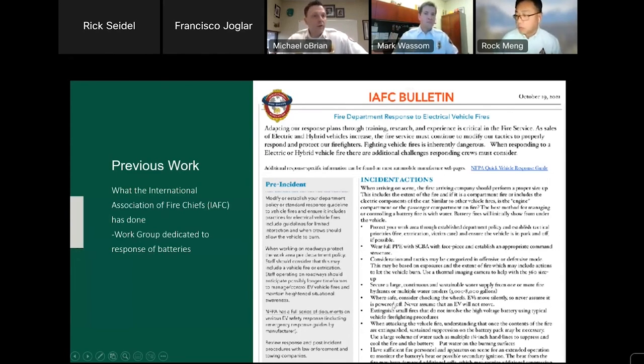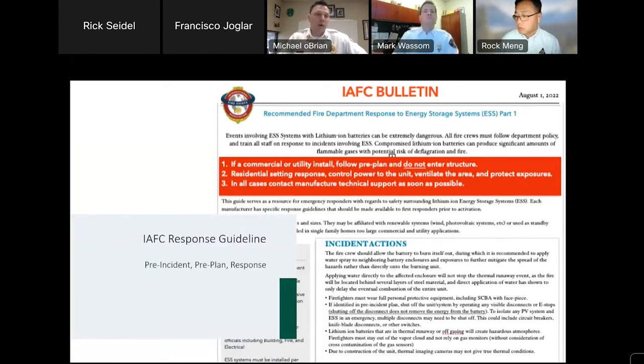So with that focus, you heard today a lot of information about what the codes and standards are doing, but there are variables that I think we've never quite seen in the built environment. We've had a lot of black and white, and a lot of certain things that we need to do. But the fire service has to be involved early in the design process. You heard some statements earlier about UL 9540 listing. That's probably one of the biggest things: making sure that the units being installed, and we're just focusing on commercial style installations, meet those minimum code requirements, specifically UL 9540, but there are requirements for when we need to get into that large scale testing.